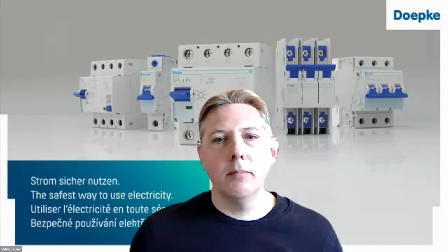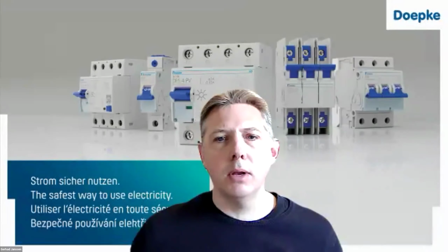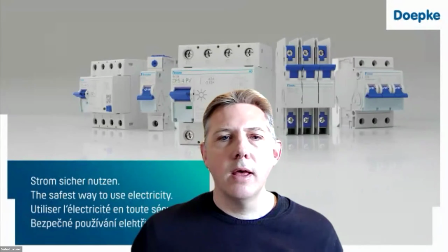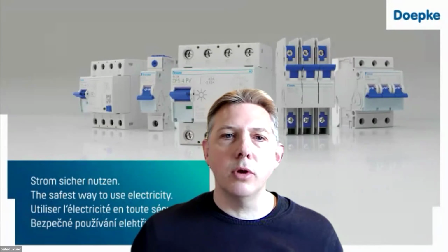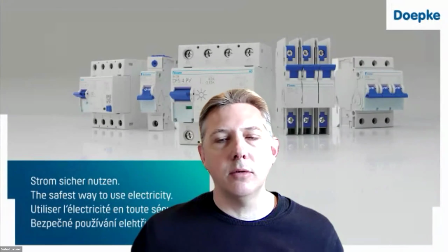What is the life of an RCD? It's hard to say. As per the norm for mechanical and electrical endurance, there are certain values. Mechanical endurance, I think, is a minimum of 5,000 cycles. Electrical endurance is a minimum of 2,000 cycles, but it does not show you the real lifetime of an RCCB. So we have different series of RCCB out in the market that are 40 years old and still working. But it absolutely depends on the installation, on the application itself.